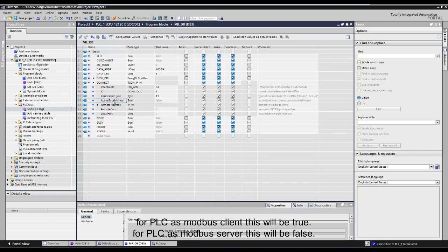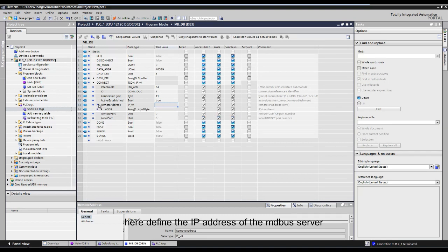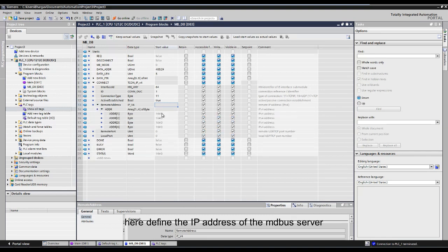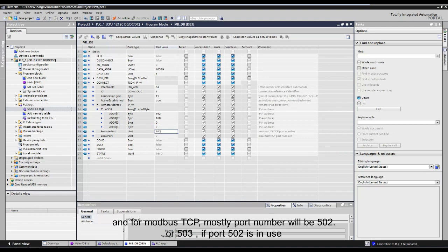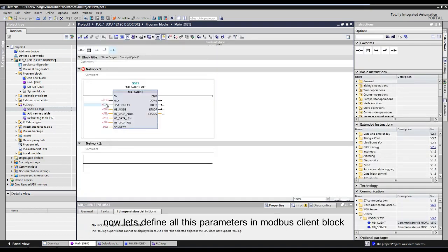For PLC as Modbus client, this will be true, and for PLC as Modbus server, this will be false. Here define the IP address of the Modbus server. And for Modbus TCP, mostly port number will be 502. Now let's define all these parameters in this Modbus client block.